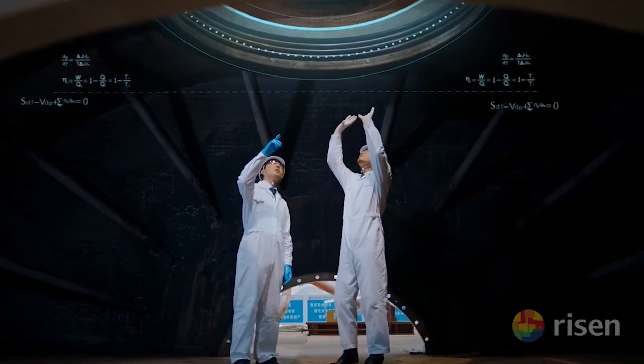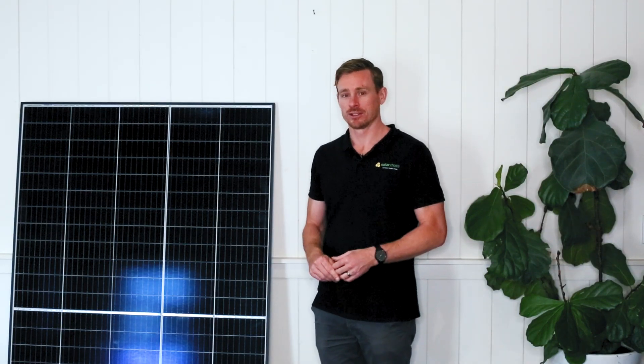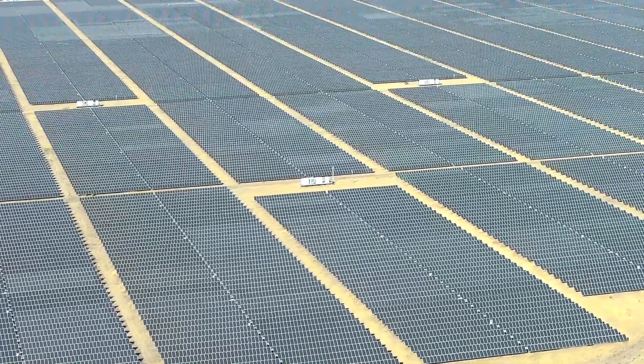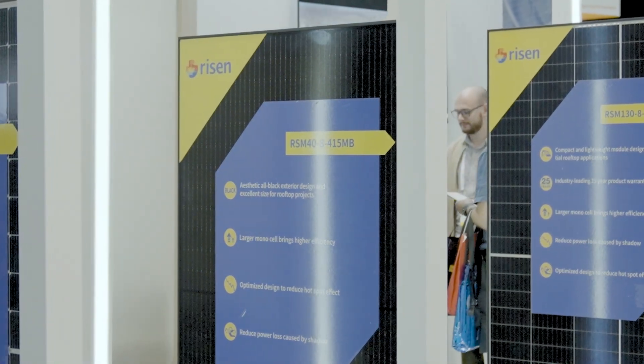The Risen solar panel comes with a 25 year product warranty and a 25 year performance warranty. As part of that, their guarantee is that in the first year the degradation rate of the panel will only be 2%, so it'll only perform 2% worse in the second year than it did in the first year. For each year thereafter, the degradation is guaranteed to be no more than 0.55%. That means after 25 years, the length of the warranty, it is still producing well over 80% of the nameplate value of the panel.